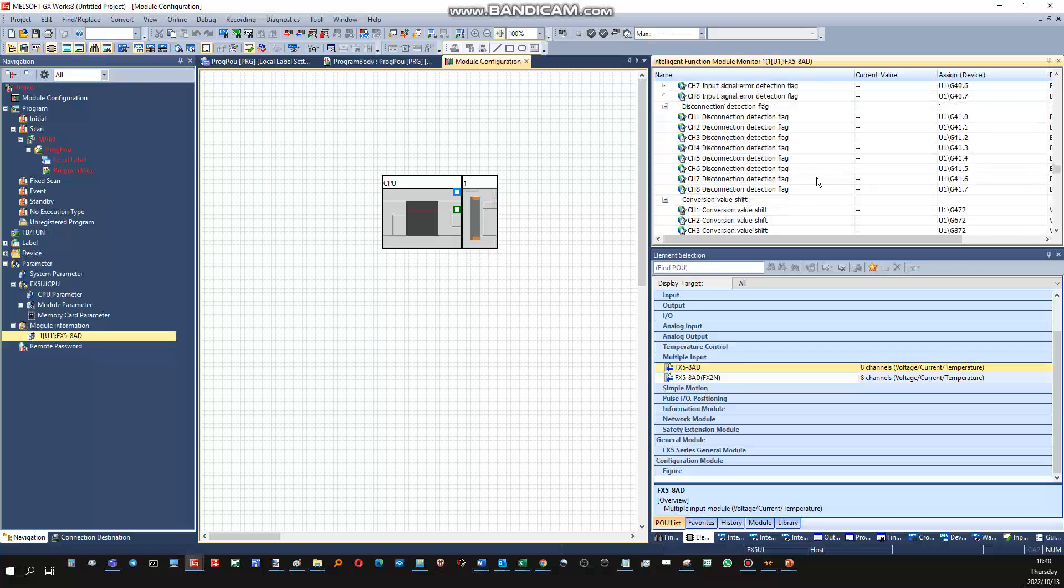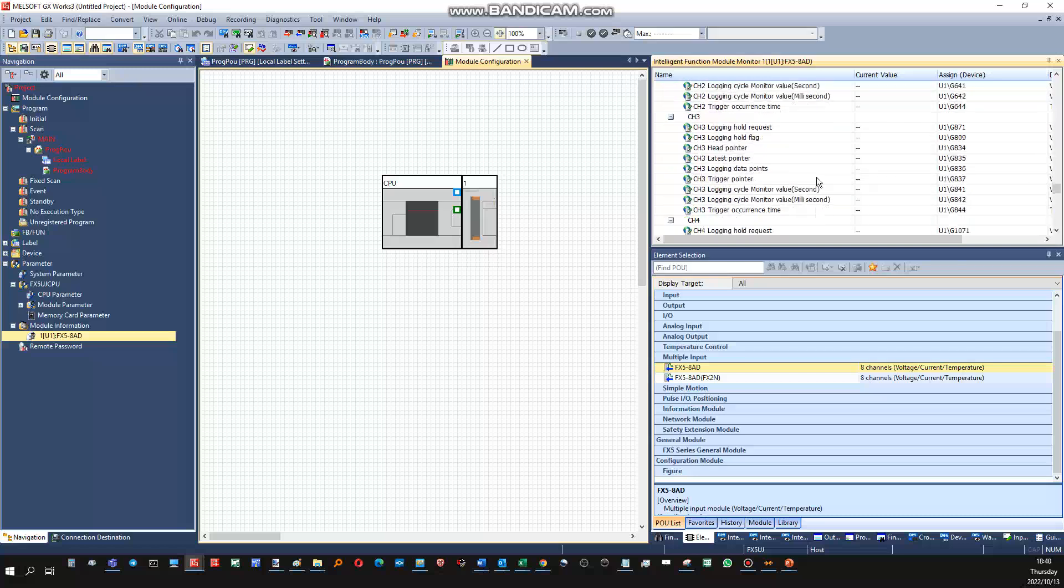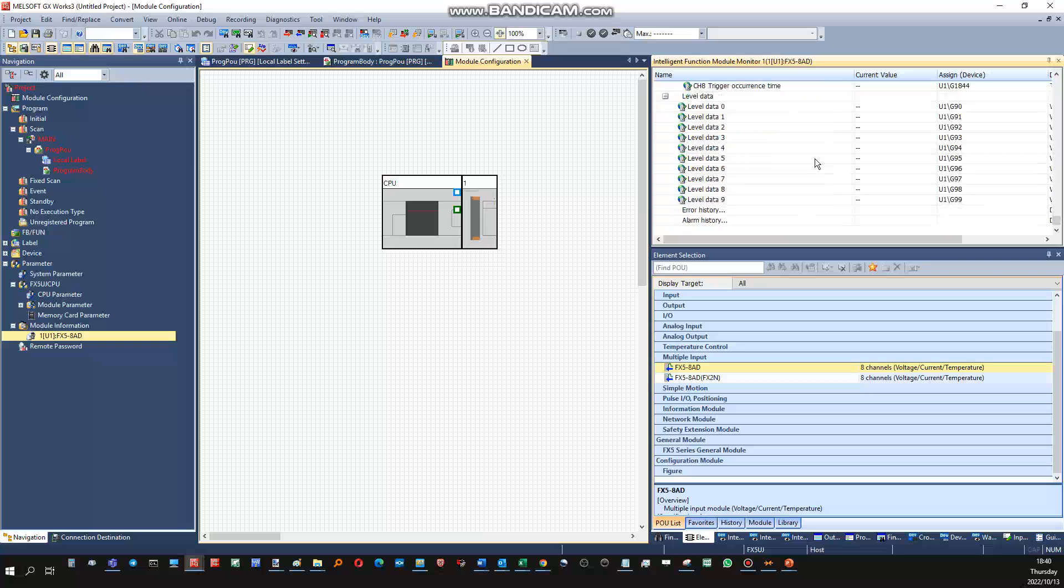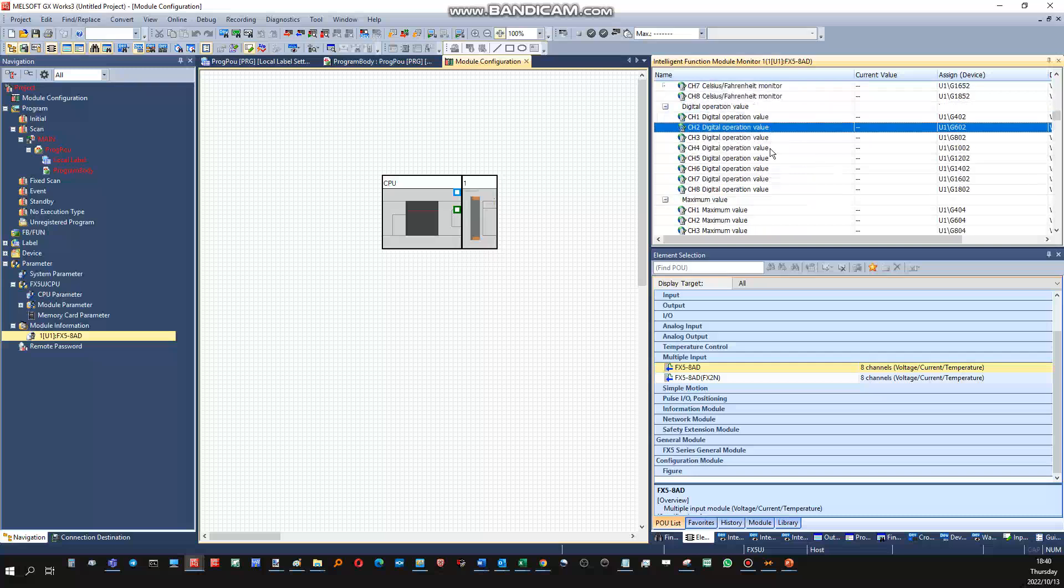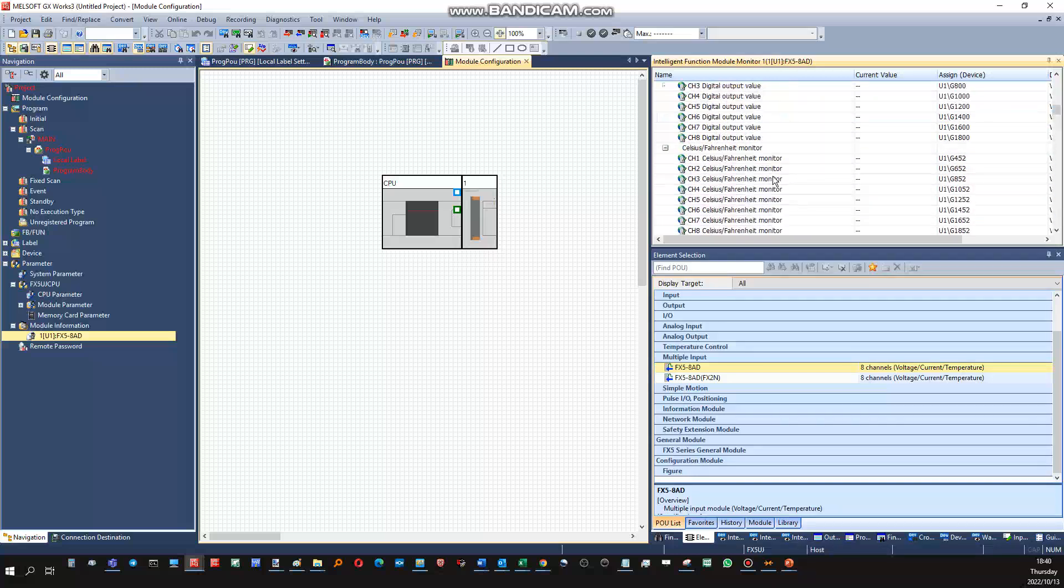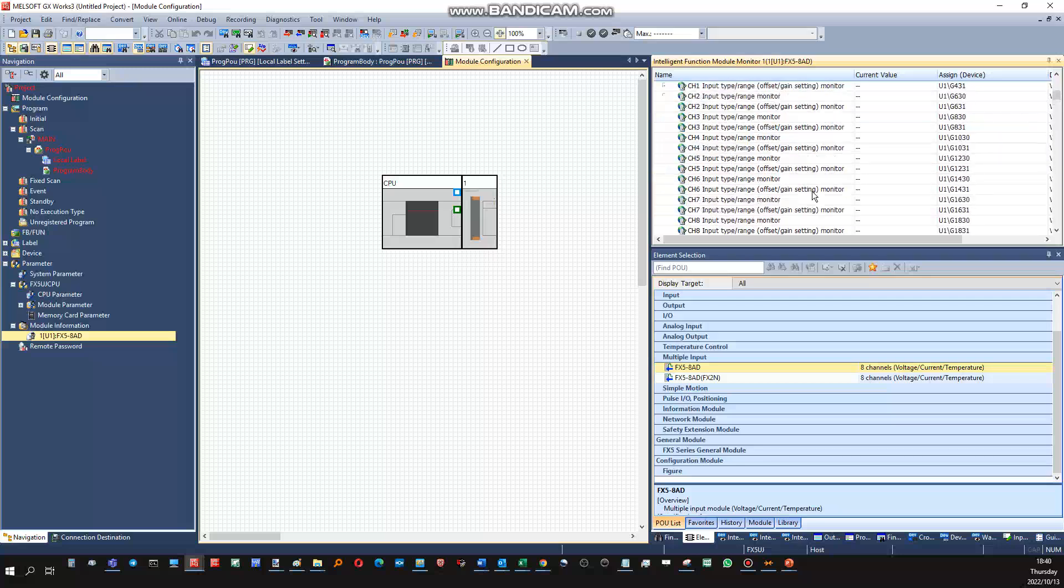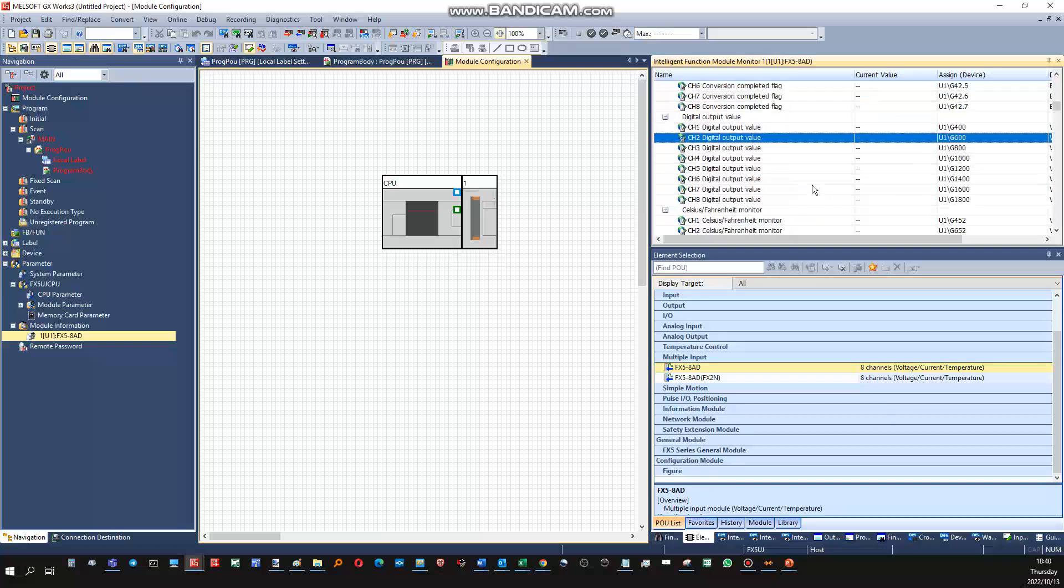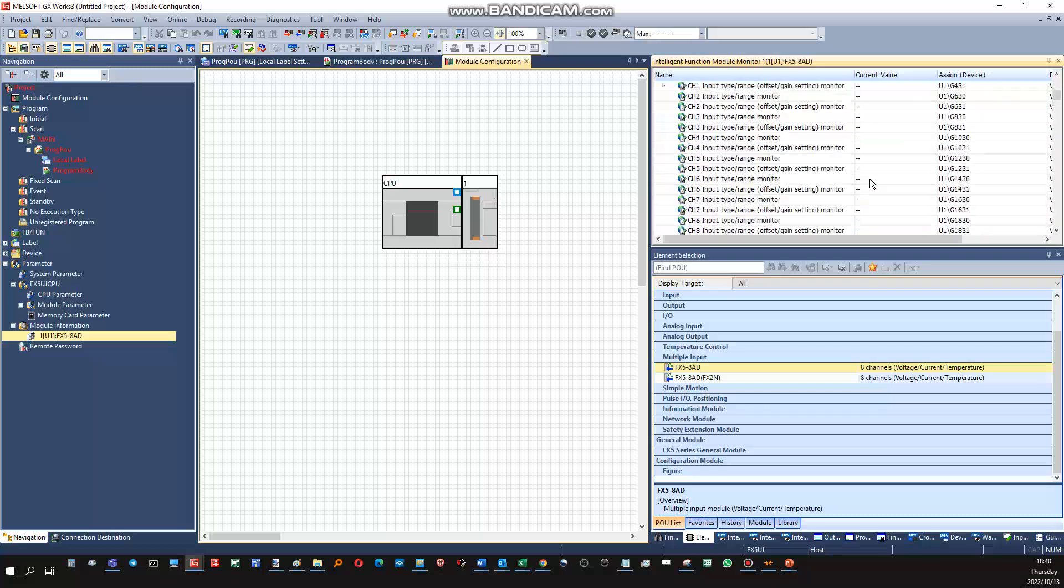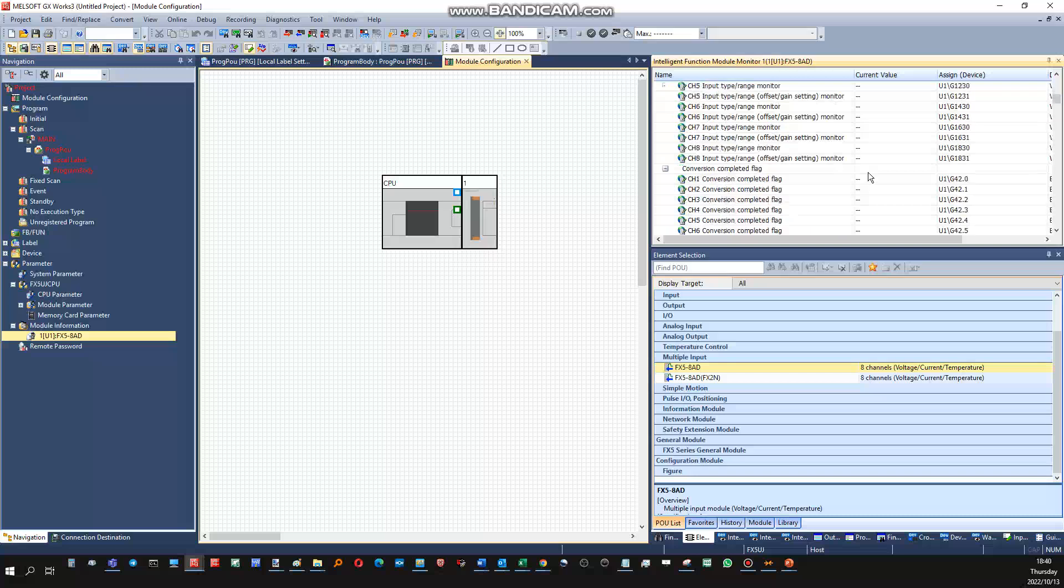So these are all alarms and scaling options, logging options, trigger options for each channel. Just see here, digital operation. So digital operation, so these ones will be the enabling of the channel. So zero will be disabled, one would be enable. And then the analog values will be stored there in a digital range, the resolution range of the PLC. It will not show the output in voltages here, it will not show the output in milliamps here, the inputs. It will be in a resolution range from zero to thirty-two thousand, etc.